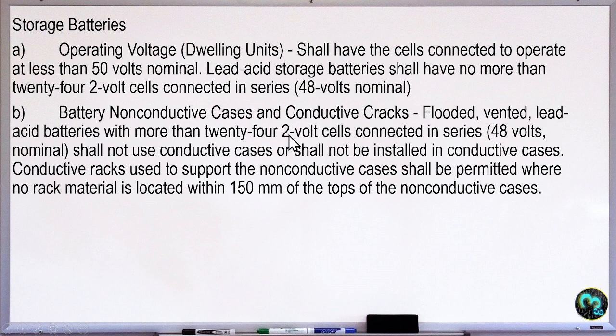So flooded, vented lead acid batteries with more than 24 2-volt cells connected in series shall not use conductive cases or shall not be installed in conductive cases. Conductive racks used to support the non-conductive cases shall be permitted where no rack material is located within 150 mm of the tops of the non-conductive cases.